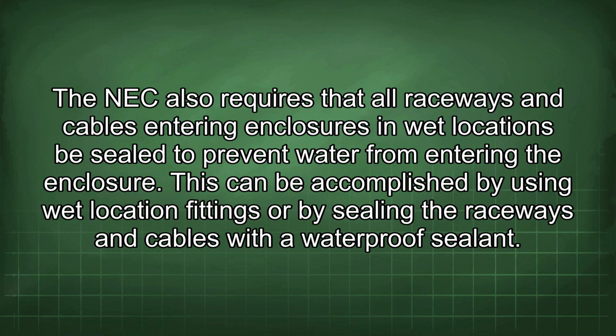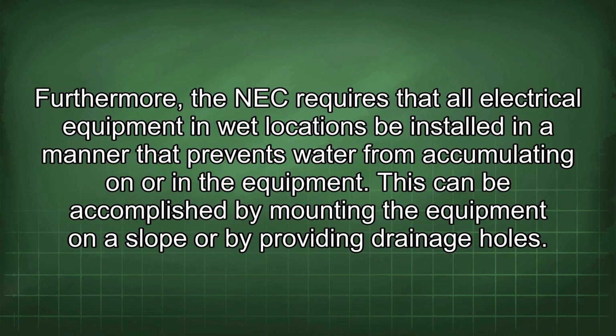The NEC also requires that all raceways and cables entering enclosures in wet locations be sealed to prevent water from entering the enclosure. This can be accomplished by using wet location fittings or by sealing the raceways and cables with a waterproof sealant. Furthermore, the NEC requires that all electrical equipment in wet locations be installed in a manner that prevents water from accumulating on or in the equipment. This can be accomplished by mounting the equipment on a slope or by providing drainage holes.